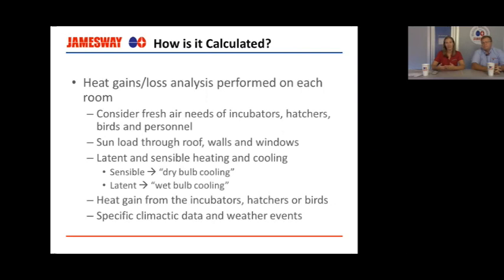So how do we calculate it? Basically, the first thing that we're doing is a heat gain/loss analysis. This is the same thing that any HVAC contractor should be doing on a house, on a commercial building, on an industrial setting. And what we're looking at is first and foremost the fresh air needs.